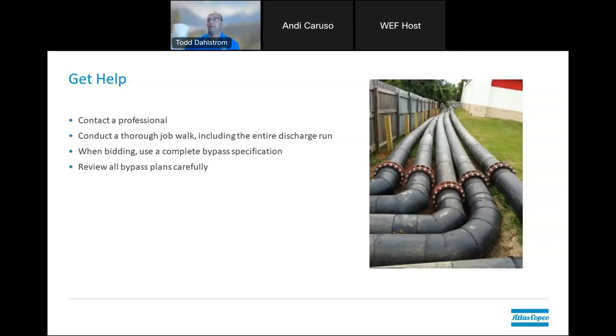Another question from Reza: Is there a rule of thumb for maximum distance and elevation from the suction point to the suction lift pump? That needs to be evaluated — it's based on all the things that come together: your flow rate, your ability for discharge piping size. There's not necessarily a restriction on how far you can go; you might just have to go to a larger pump or a larger pipe, because the further you go, you get an increase in friction loss. There are multiple pump sizes from 2-3 inch pumps all the way up to 24 or 30 inch pumps. It is a case-by-case evaluation, and we'd be happy to discuss specifics at a later date.